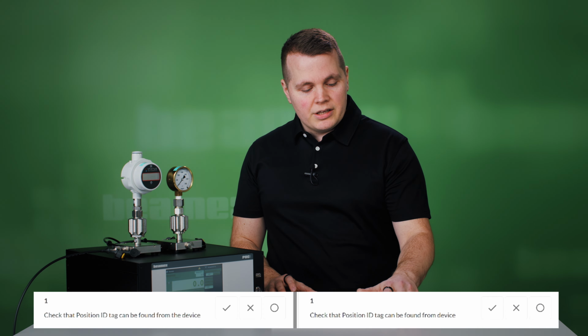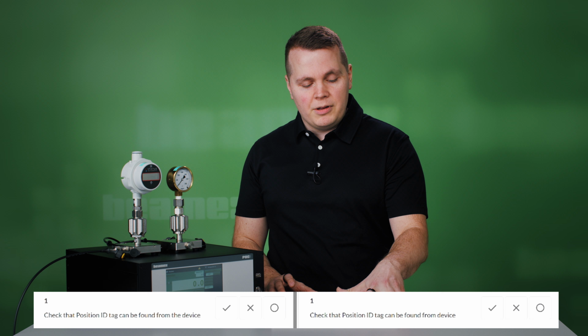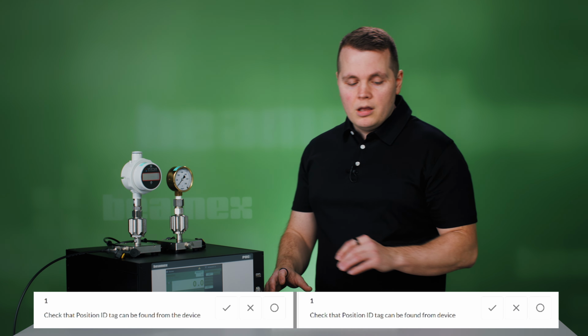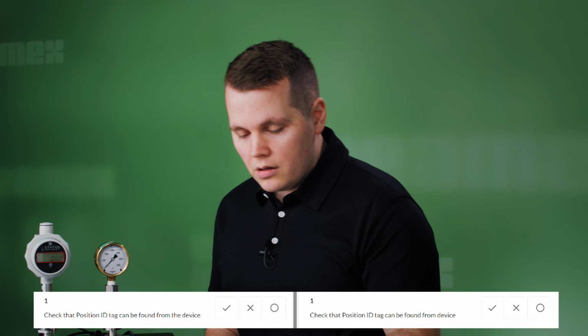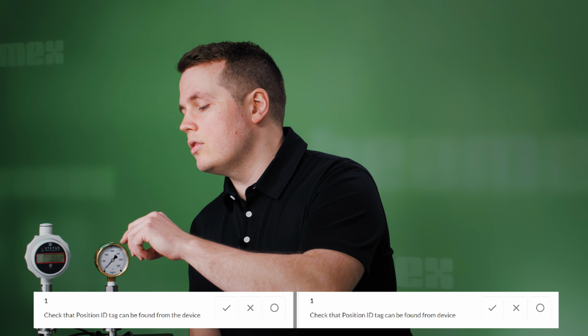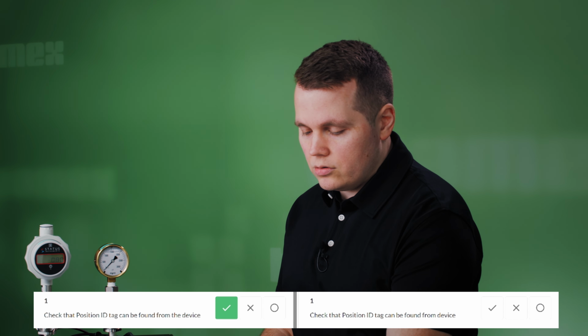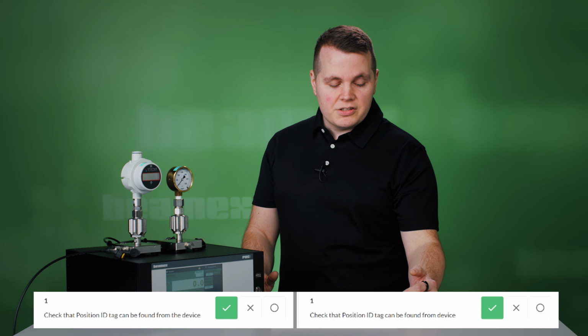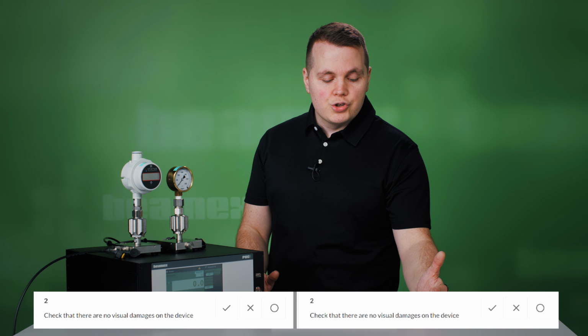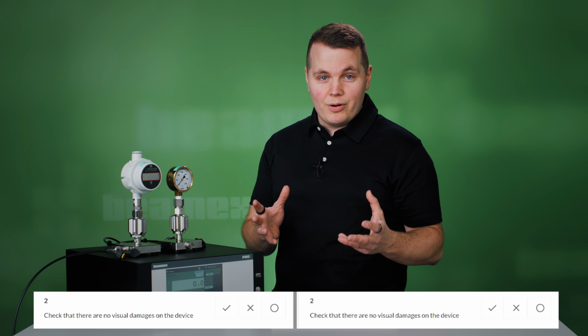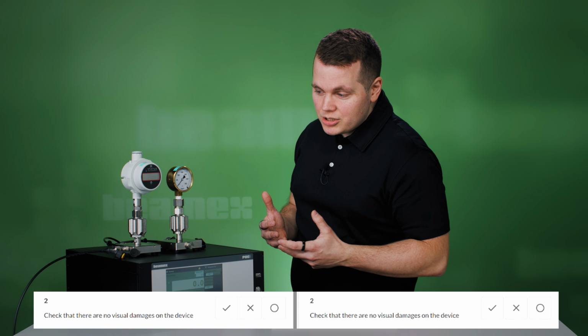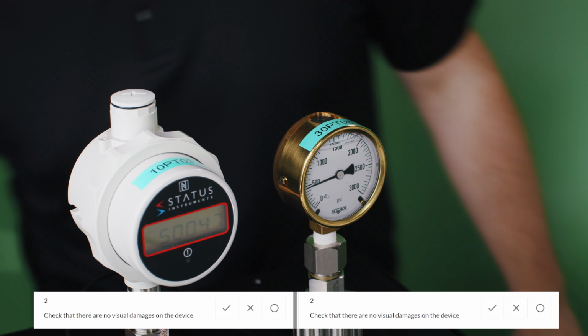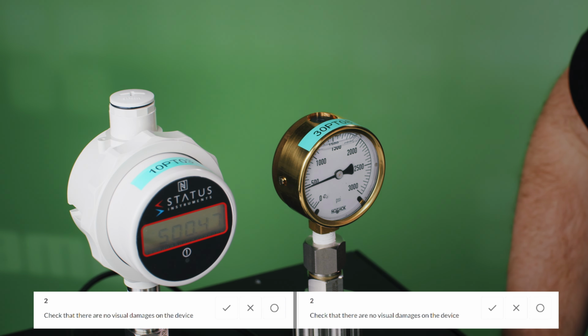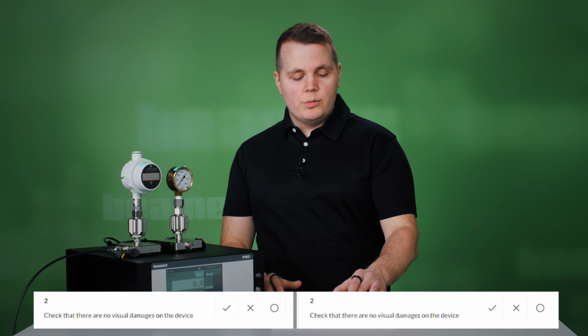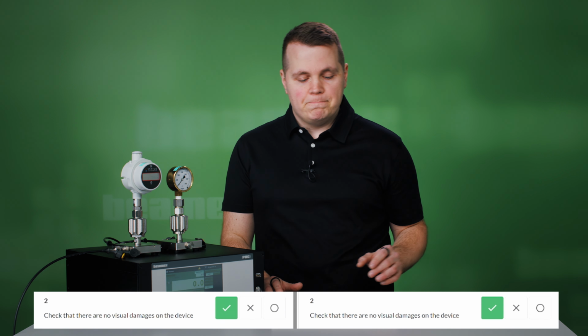The first check is check that the position ID tag can be found from the device. I've got 10PT03, 10PT03, 30PT08, 30PT08. That's a pass on both. The second checklist item is check that there are no visual damages on the device. Now these are brand new devices, so I would expect no damages, but let's check them out either way. Both look good to me, so I will click on pass and pass.